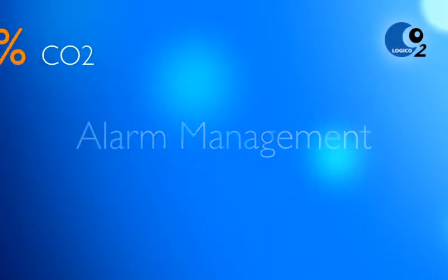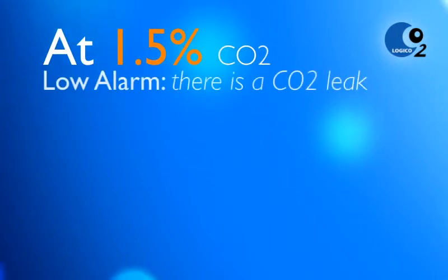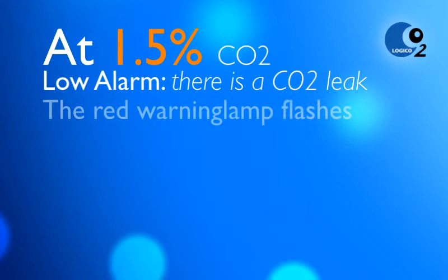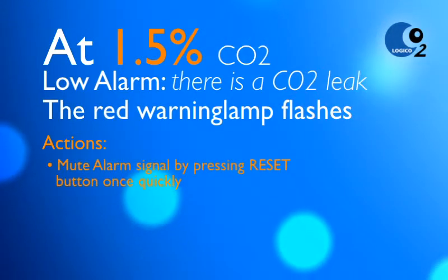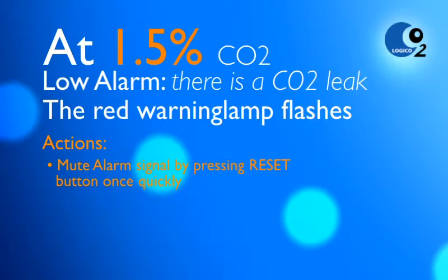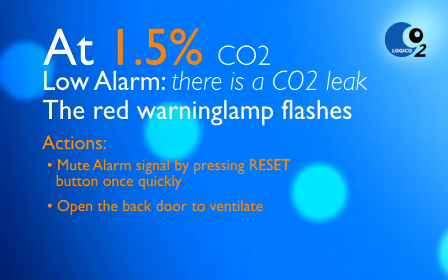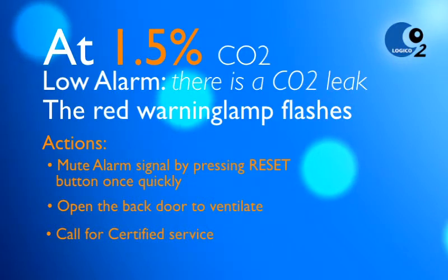At 1.5%, the system makes a low alarm. There is a CO2 leak. Mute the alarm signal by pressing the reset button once quickly. Then open the back door to give extra ventilation and call for service.